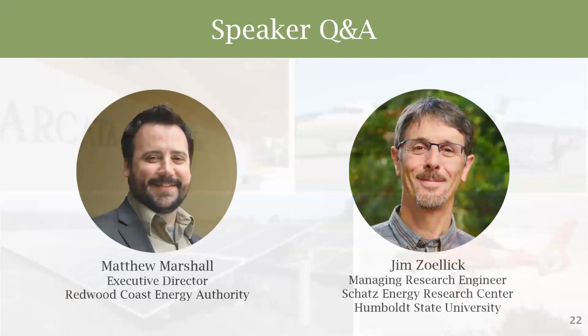Matthew and I will do the little dance of replying. One unique aspect to this microgrid is that the generation and storage asset has been sized very large compared to the load on the islanded portion of the grid. Those 20 accounts that make up the microgrid when islanded have a peak load of about 330 kilowatts and an average load somewhere in the 200s kilowatts. The PV and battery is sized at 2.2 megawatts, and up to 2.5 with the net metered array, so it's way oversized. You wouldn't size it that much just for those local loads, but it's sized for wholesale market participation and as a local renewable energy project for the CCA.